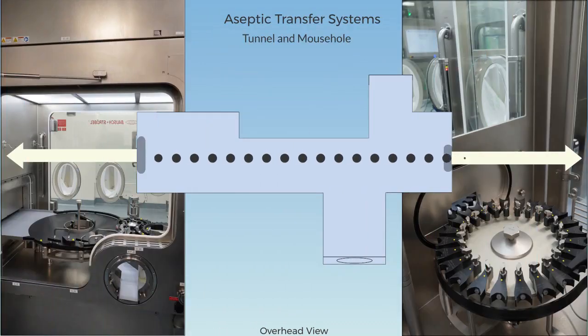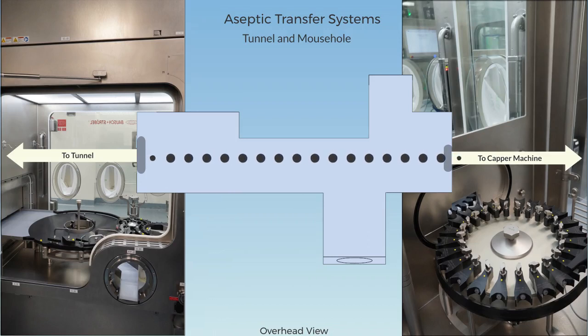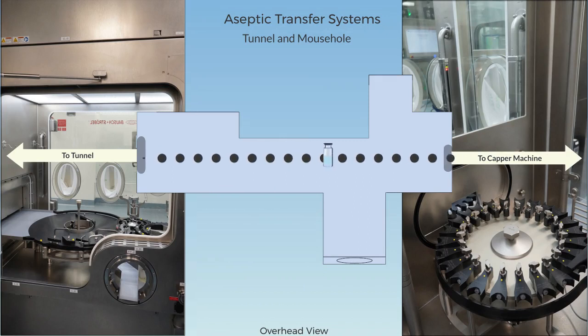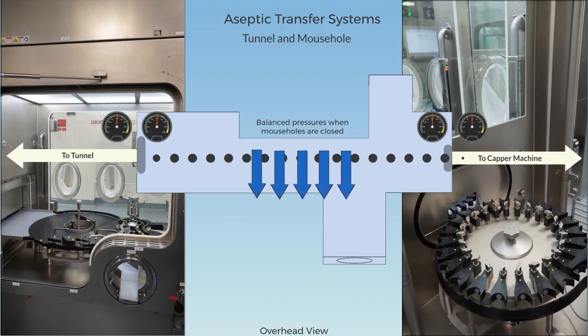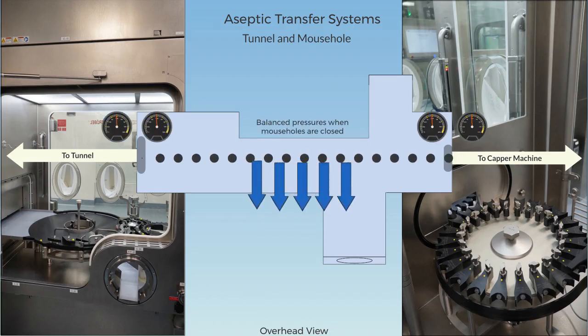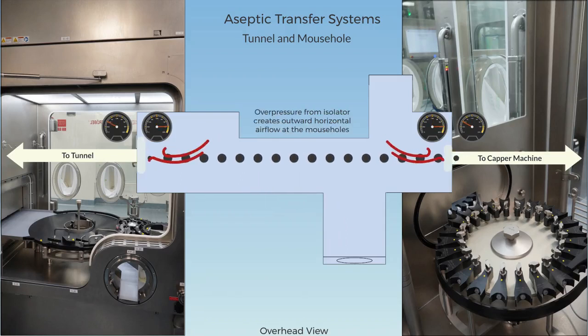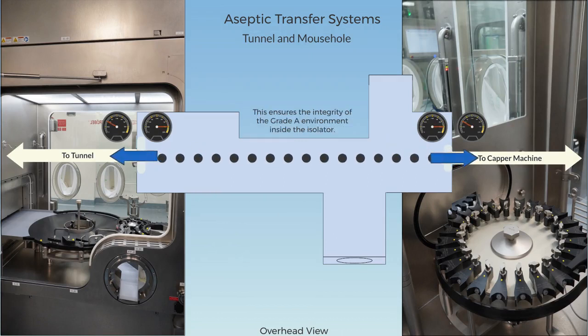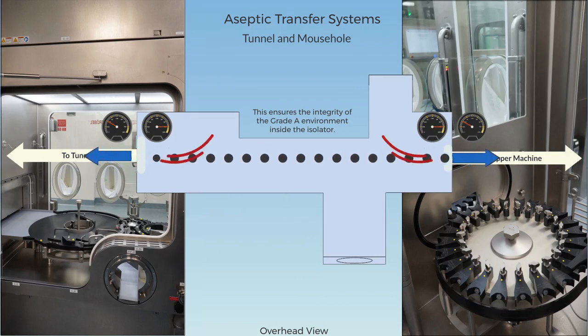The Line 2 isolator uses aseptic transfer systems to maintain the sterility of the product as it moves through the filling process. The sterilized empty vials are loaded into the filling isolator via the sterilization tunnel, and the filled vials are transported to the capper machine via a mouse hole. The vertical airflow remains a constant velocity when the openings are closed. When opened, the air velocity increases due to the differential pressure of the isolator to the surrounding area. However, because of the defined pressure cascade, the airflow at the openings is horizontal in the indicated direction and the integrity of the isolator is maintained.